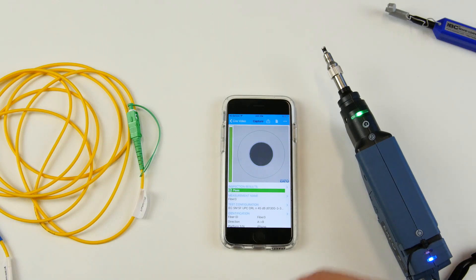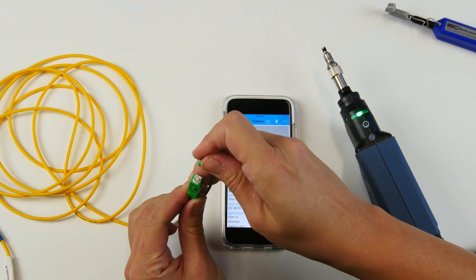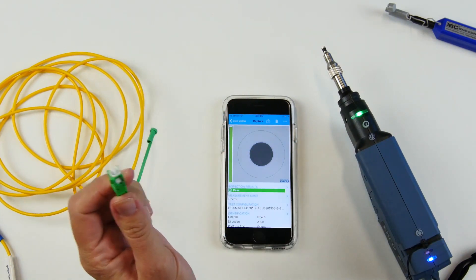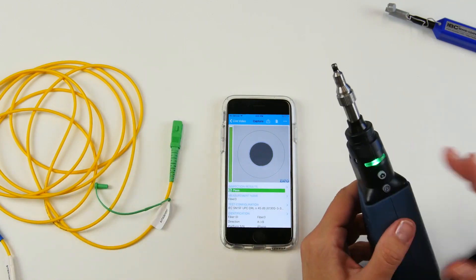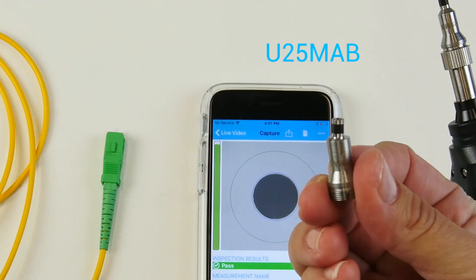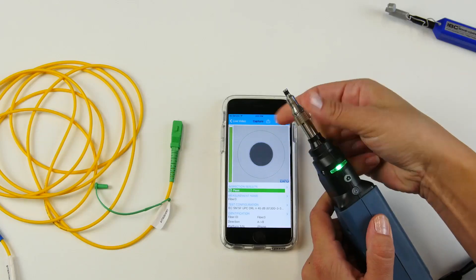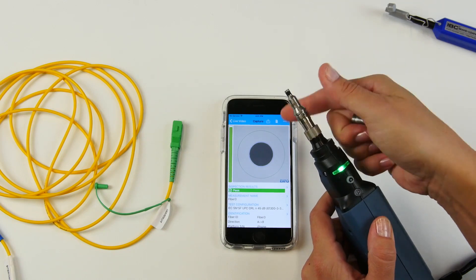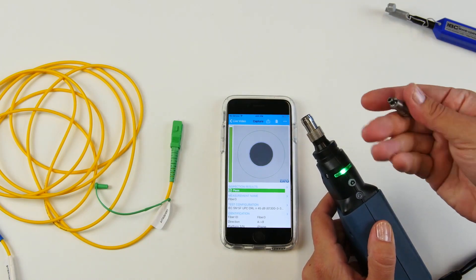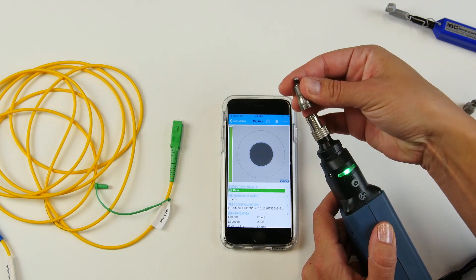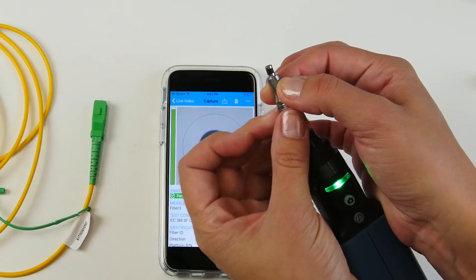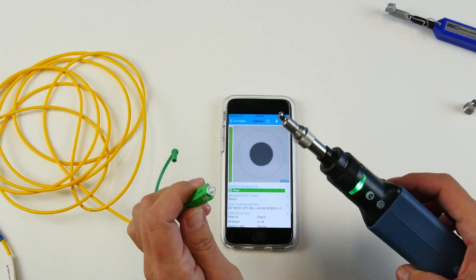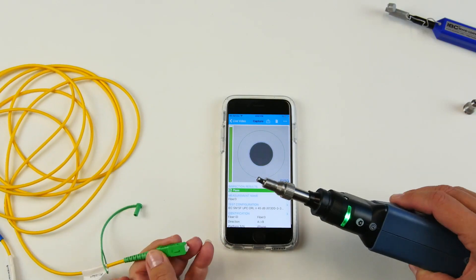For different types of connectors, we actually have to use different tips on the probe. For example, an APC SC connector will require this type of tip. Simply remove this one, switch it up. And you are ready to test.